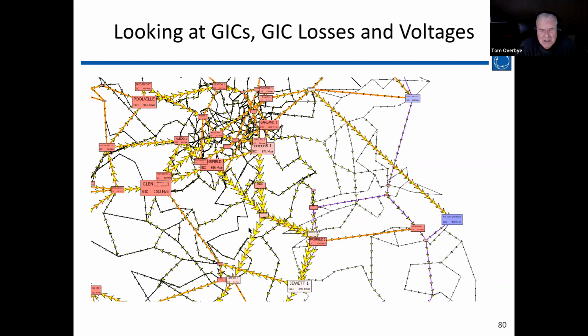I didn't mention neutral blocking devices, not because I'm against them—there's just not a lot of them out there. But from a study point of view, if somebody said, hey, I want to study this GIC scenario or this HEMP scenario and put a neutral blocking device here, here, or here, we could set them up as Scott said, as an initial condition, and then do a study with it either in service or out of service.